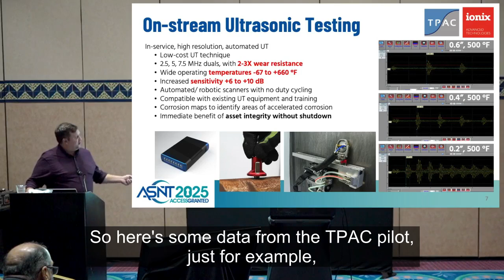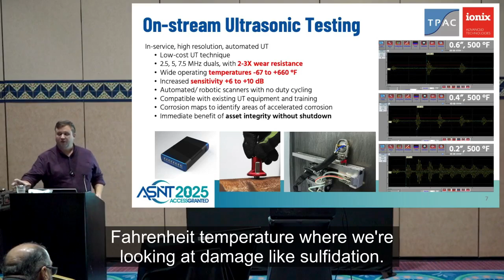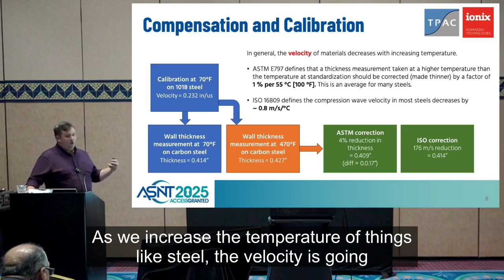We're in the TPAC room, so here's some data from the TPAC pilot, just for example, showing you what the sort of typical responses are at that kind of 500 Fahrenheit temperature, where we're looking at damage like sulfidation. So lots of people have sulfidation damage, and we spent a lot of time working with owner-operators to make sure that we can get accurate and reliable, repeatable wall thickness measurements by doing things like coming up with procedures for compensation and calibration. Give you some examples.